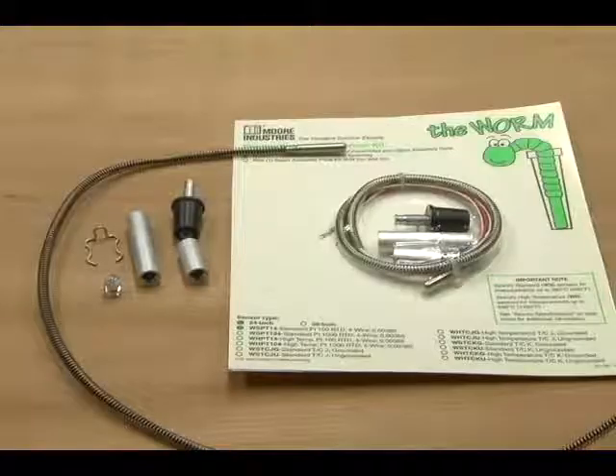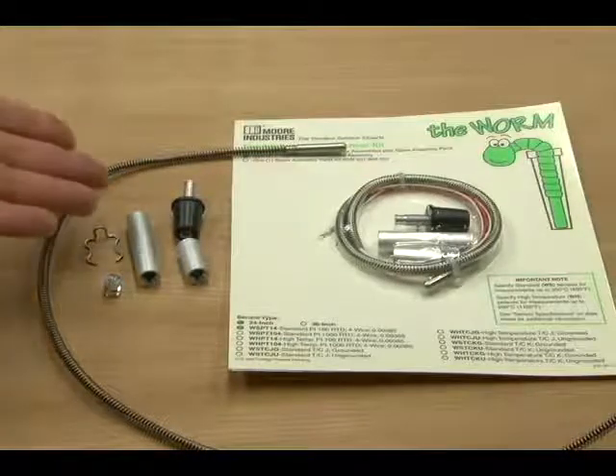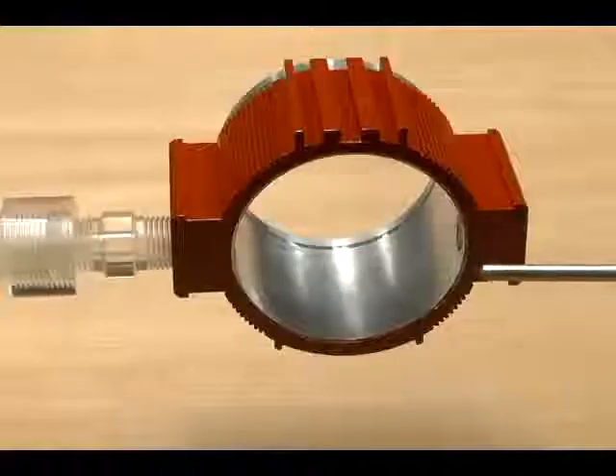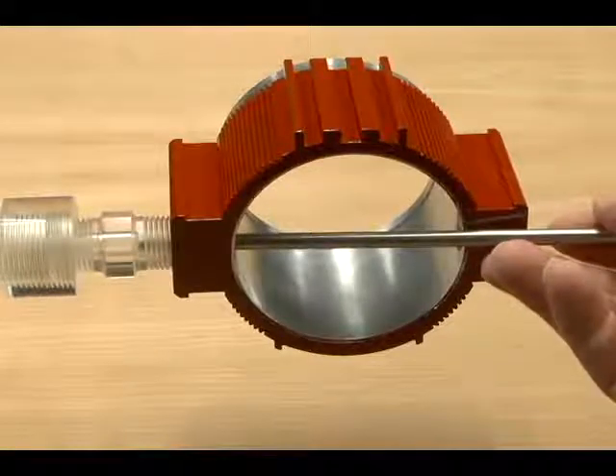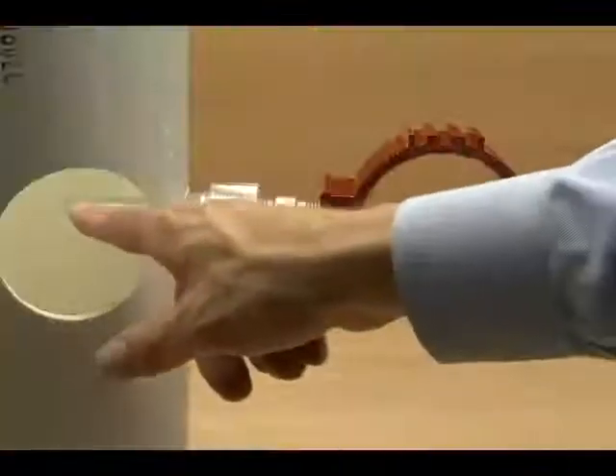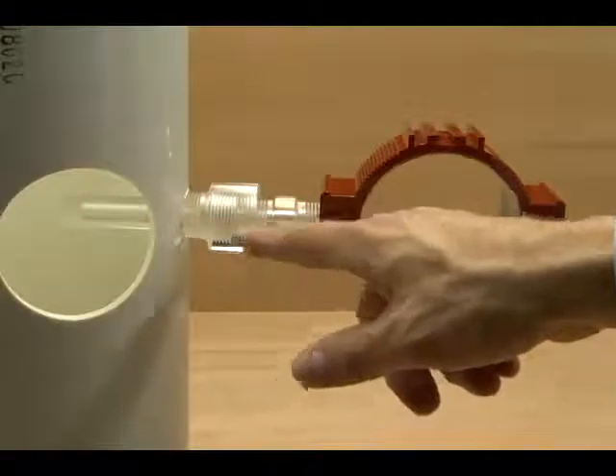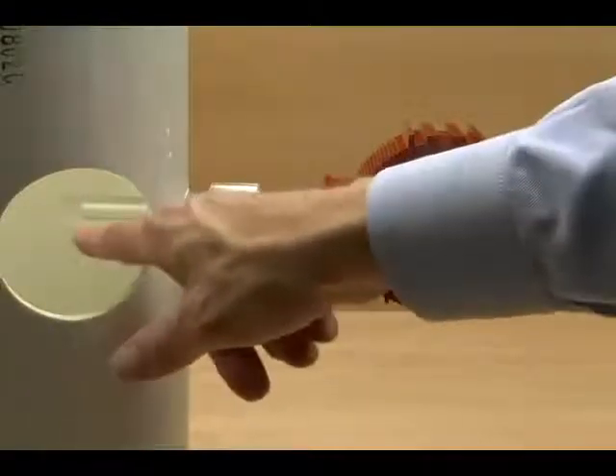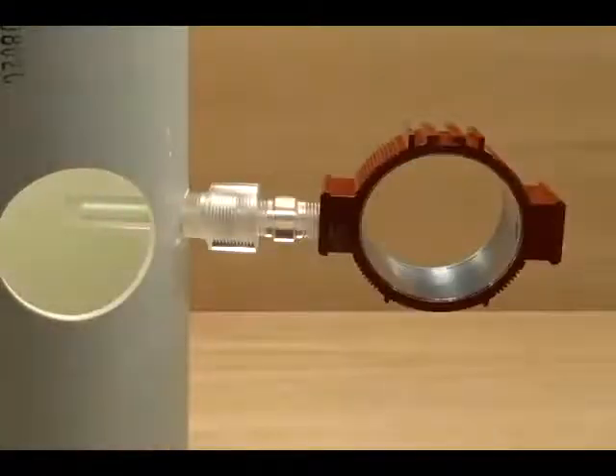So let's see how it works. The kit includes several different components that help with the back-end termination of the spring and spacers for use in larger diameter thermal wells. Let's go back to that first thermal well and transmitter housing we looked at. For purposes of demonstration, we've made the thermal well out of clear plastic. We want to insert a new probe without taking off the housing, which is no trouble for the worm.